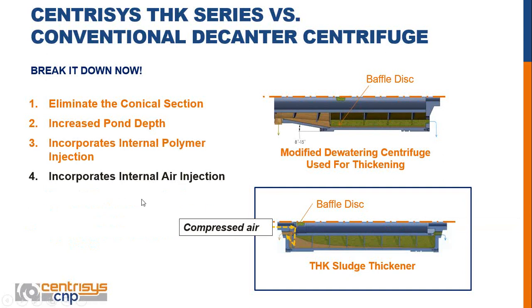And the final thing is this injection of air into the machine. On the left-hand side of the machine, we're adding compressed air in. It's coming in this disc here, and as the solids come around the disc, the air gets added in, and it actually helps push the solids out. What this is doing is really adding a layer of control for how thick the cake is going to be coming out of the machine. So the more air you add, the faster the material flows out of the machine, and the thinner the cake is going to be. The less air you add, the slower the solids are going to leave the machine, and the thicker they'll end up being.